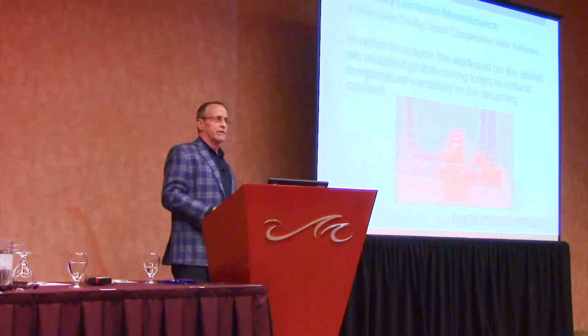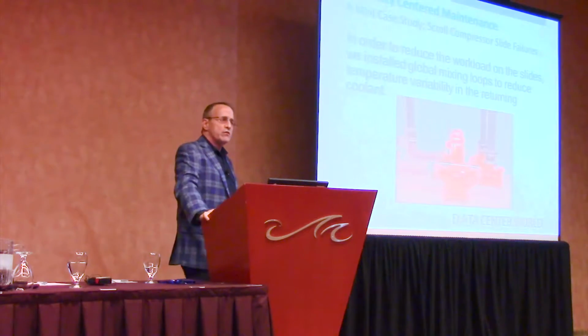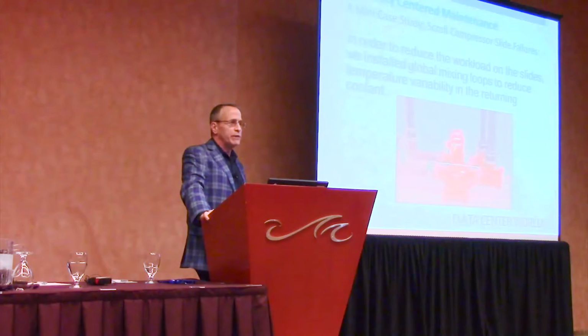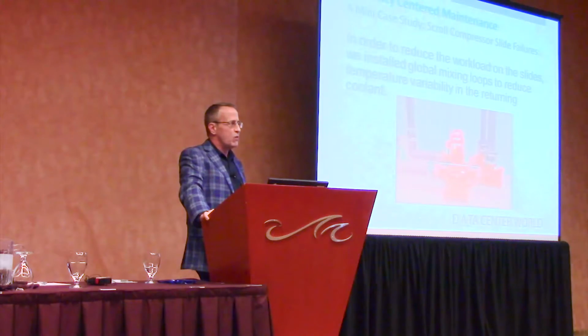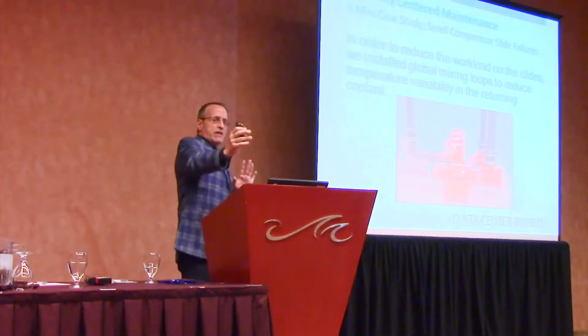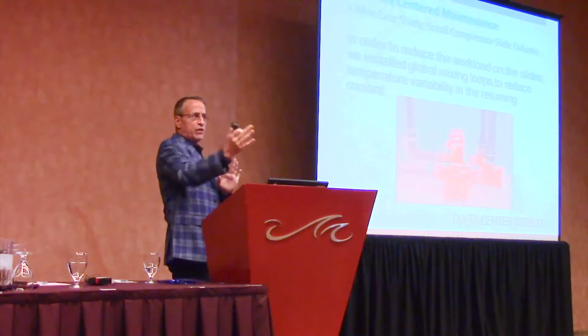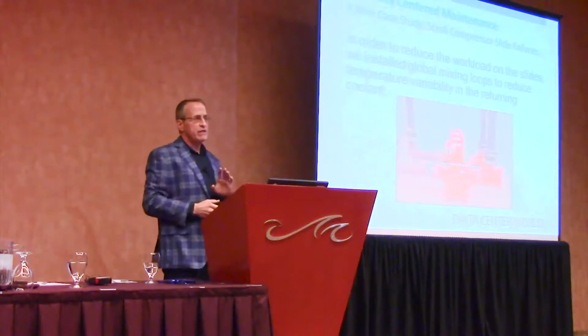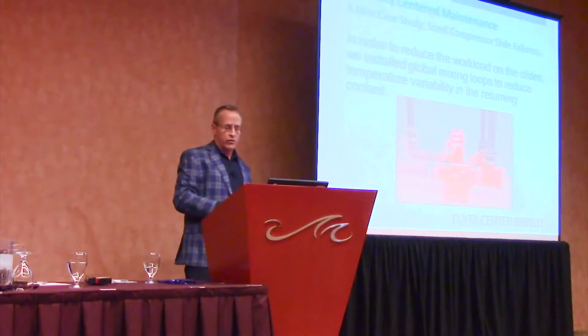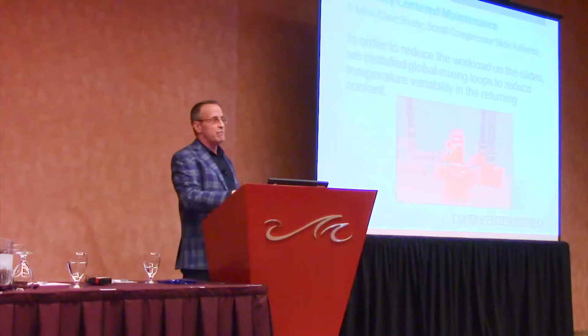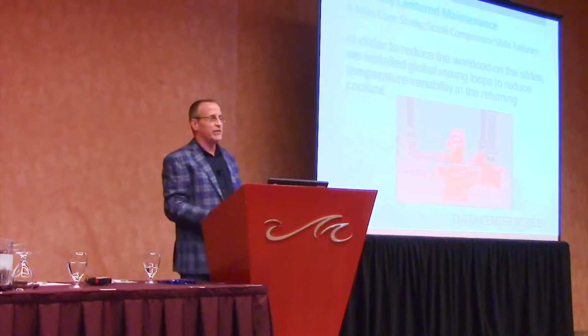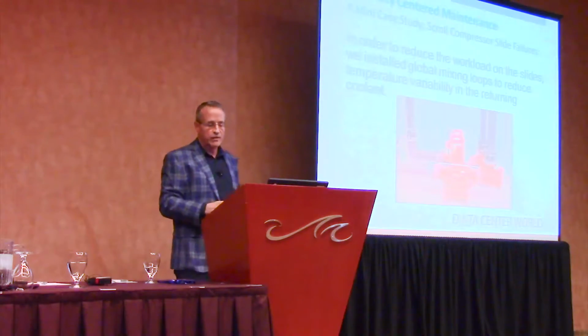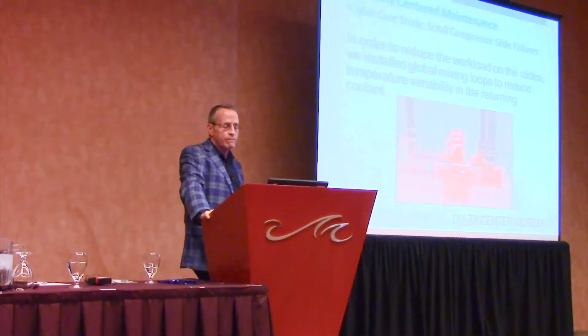Things go crazy. So we introduced the concept of a mixing loop, and we run the water in between the supply and return loops on the floor and the chiller plants at 1,500 gallons per minute. And of course, you can tell looking at that, this is one redundant pair. It has a redundant pair downstairs. We can operate without it, but things get a lot less efficient.